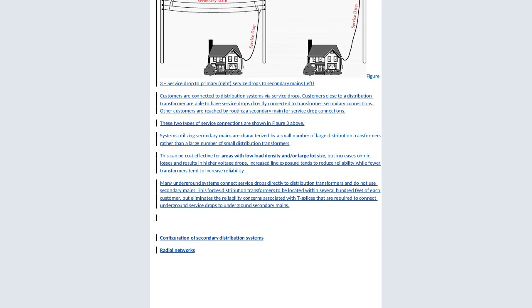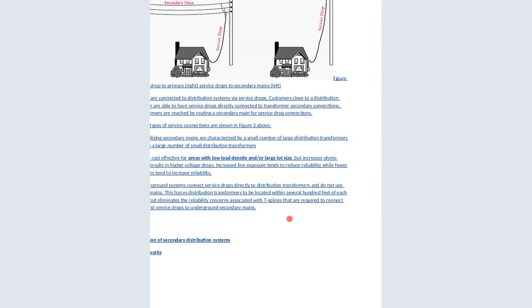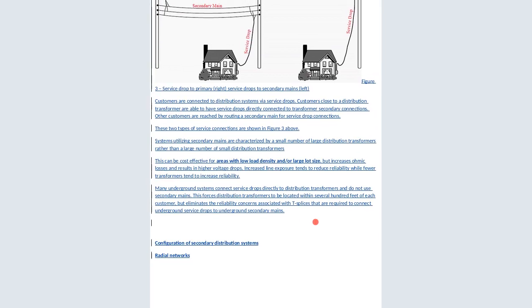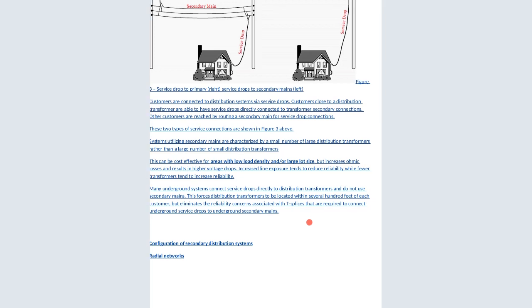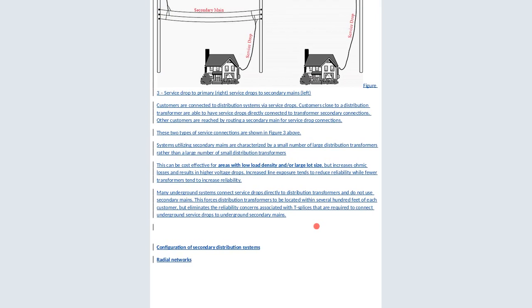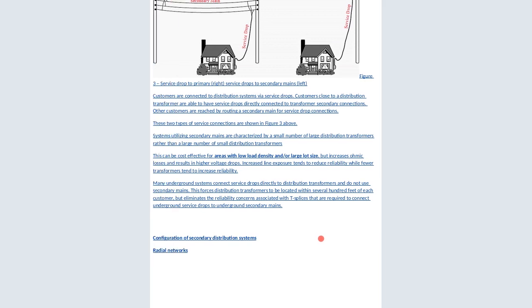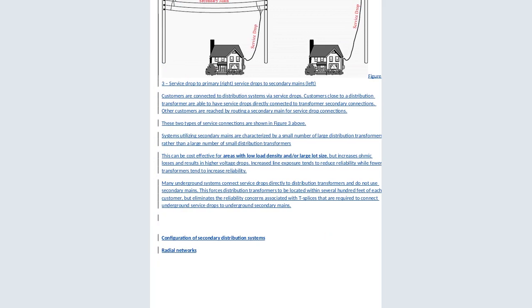Many underground systems connect service drops directly to distribution transformers and do not use secondary mains. This forces distribution transformers to be located within several hundreds of feet of the customers, but eliminates the reliability concerns associated with the T-splice that is required to connect the underground service configuration. Now we have talked about the topologies.